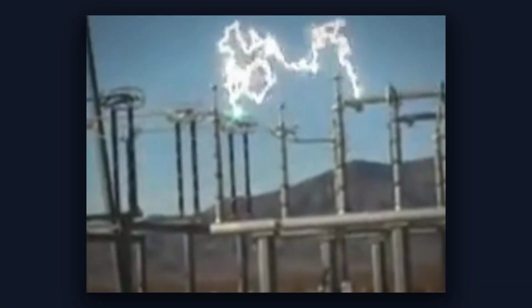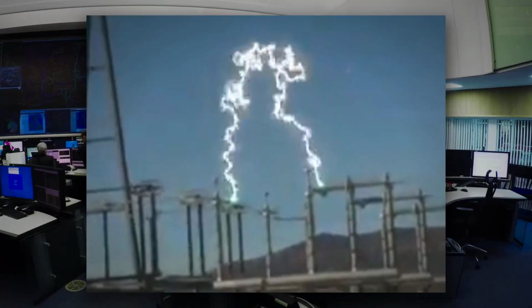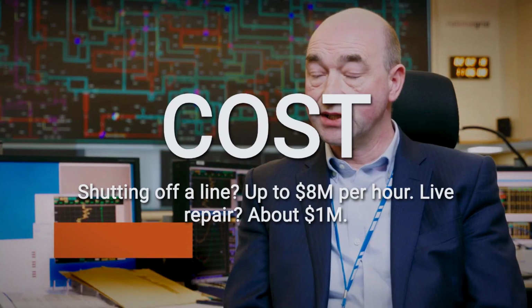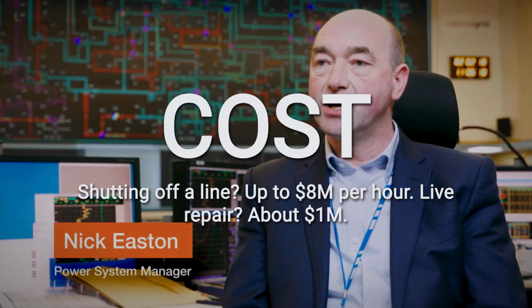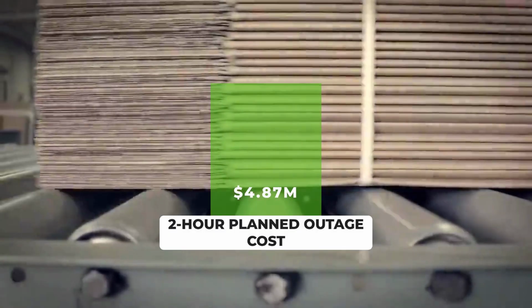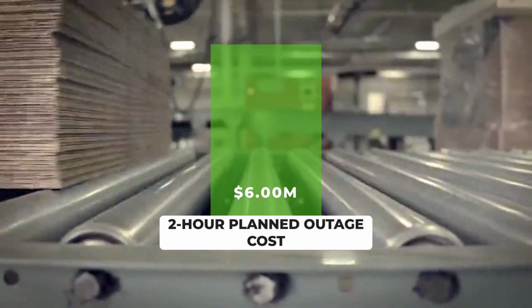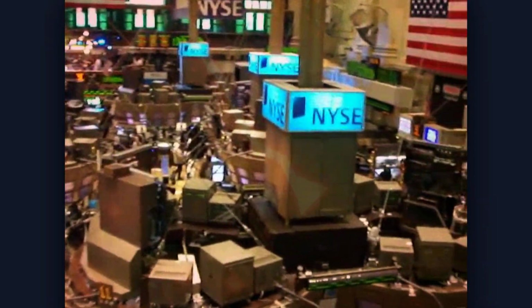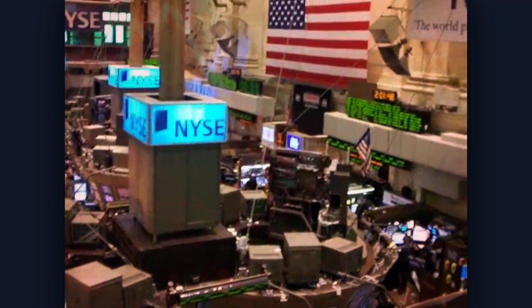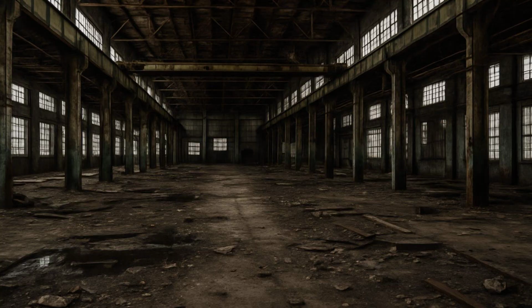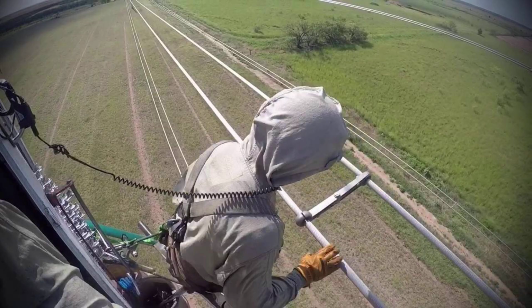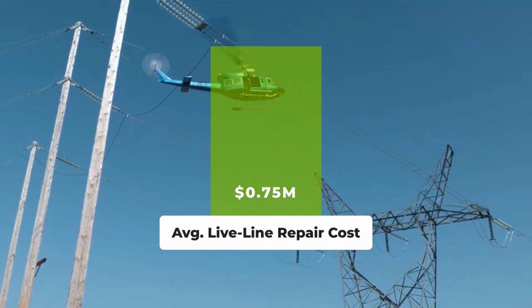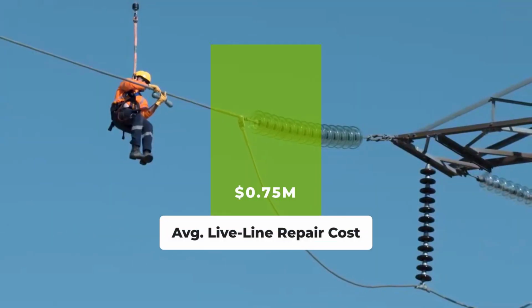A planned shutdown of a high-voltage transmission line triggers a direct economic calculation in every control room. The cost of a single event, factoring outage compensation to industrial customers, market penalties, and switching logistics, typically ranges from $3 to $8 million. By contrast, a live line repair, even with helicopter crews and specialized equipment, averages between $500,000 and $1 million per incident.